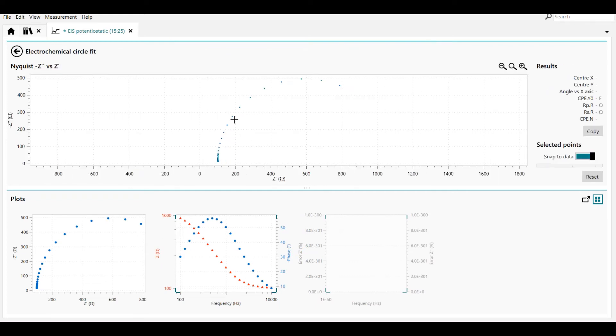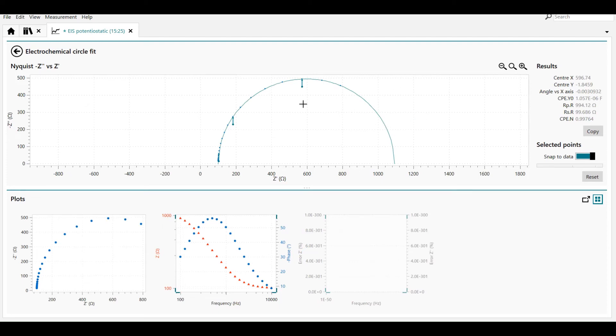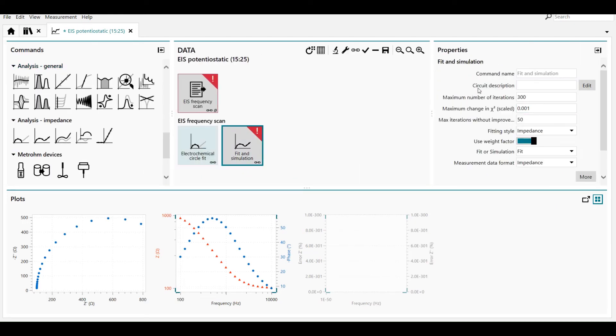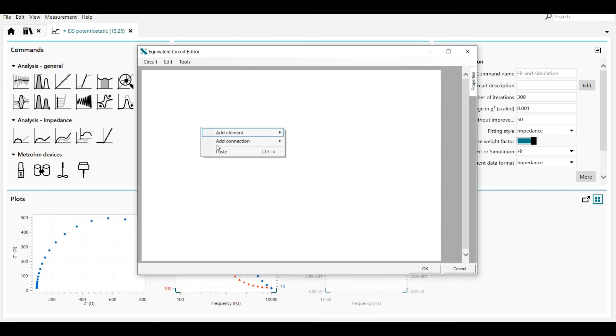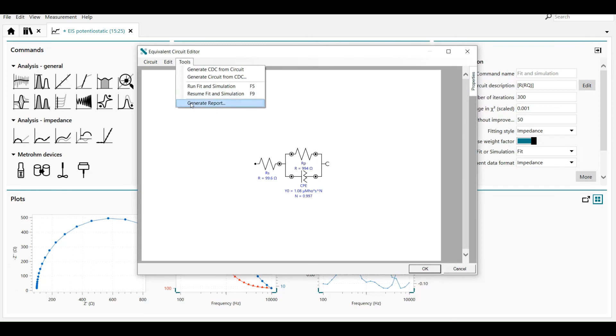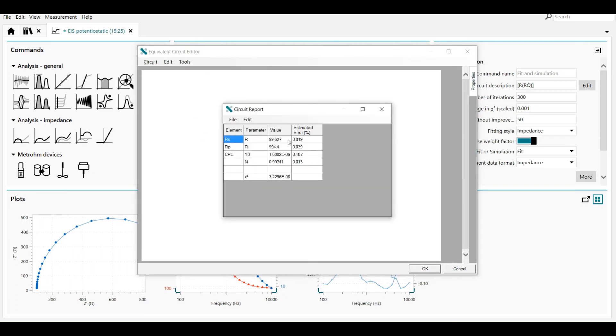First we do electrochemical circle fit — we select a few points on the graph. The semicircle is constructed and here we find the resistances and capacitances of the circuit. We can copy the information and use it in the fit and simulation routine. We can edit the circuit description and in here you'll find a paste command. Press OK and then we'll start fitting the data. In the fit and simulation routine under Tools you can also generate a report showing all the values of each equivalent circuit element.